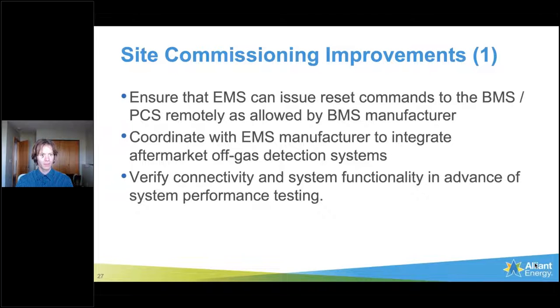Highlighting some site commissioning improvements that we have after seeing the system in operation. One of the really important things is that the EMS should be able to issue reset commands to the BMS and PCS remotely, at least as much as allowed by the BMS and PCS manufacturers. We've seen a number of occasions where site personnel have had to visit the site to restore the system to service after a blink or outage on the switchgear or feeder breaker trip.